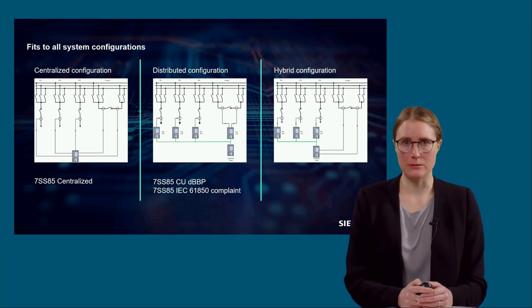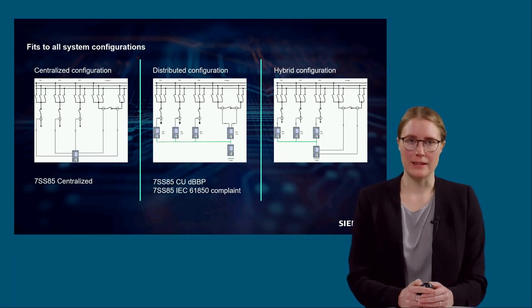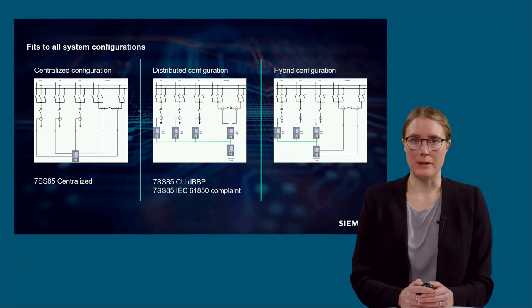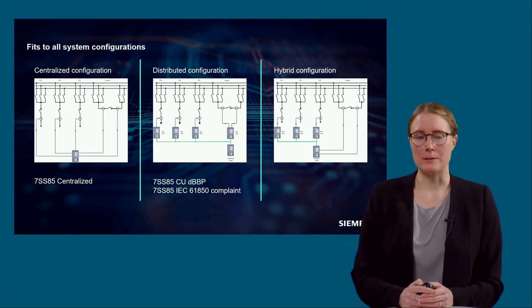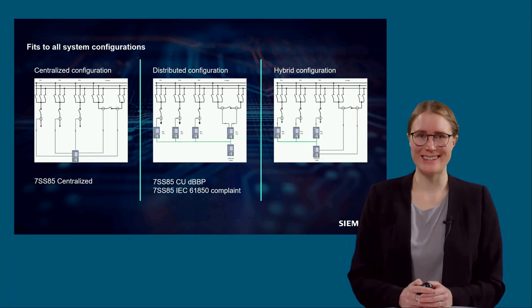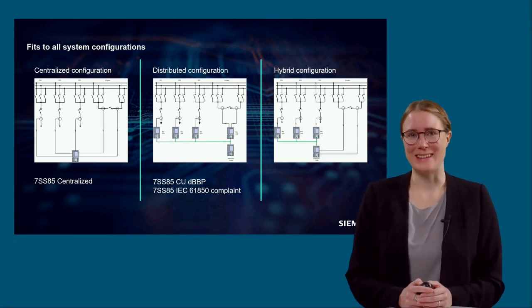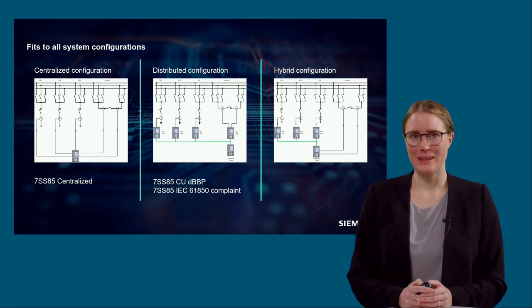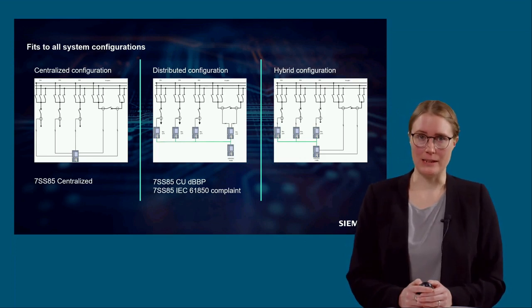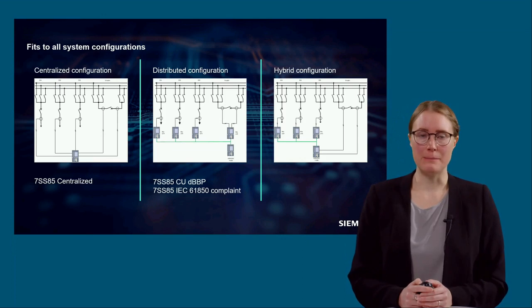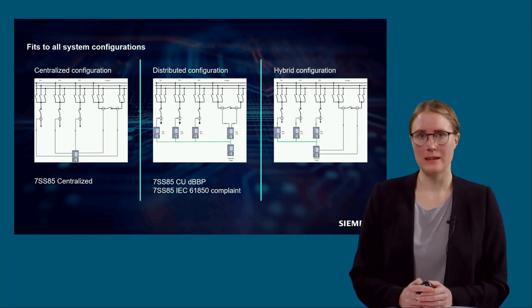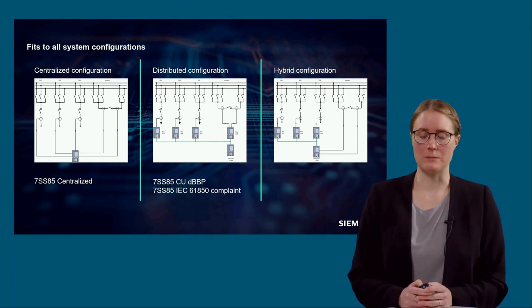The 7SS85CU distributed busbar protection solution is also a process bus solution based on the IEC 61850 protocol. Flexible streams are used, but with the fixed stream type IEC 61869-9. The sampling rate configuration is set to 4000 Hz and 1 ASDU. For the bays, only proxy elements are available. The engineering is simplified following an automated process. It is additionally possible to configure user-defined GOOSE messaging. With this solution, it is not possible to integrate third-party merging units.